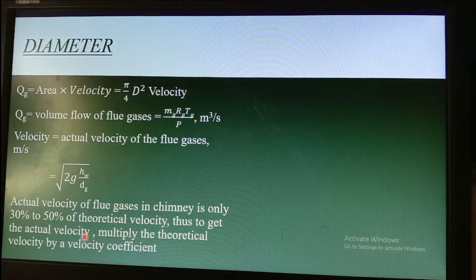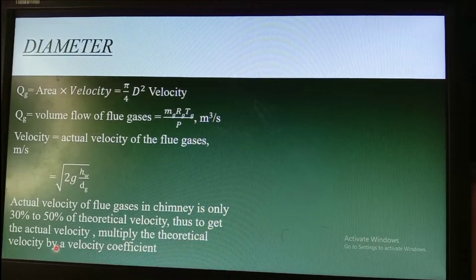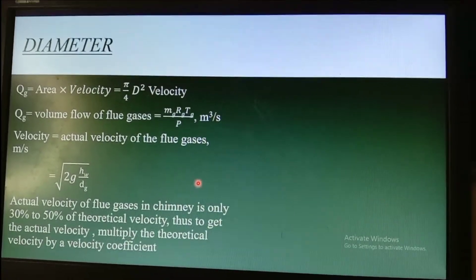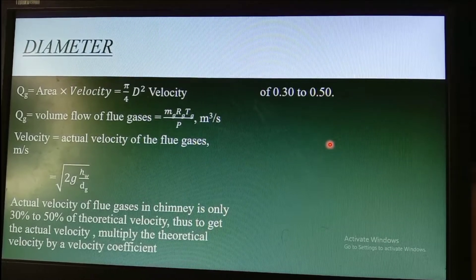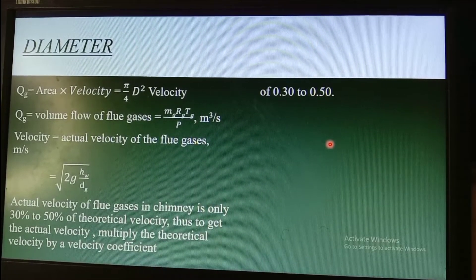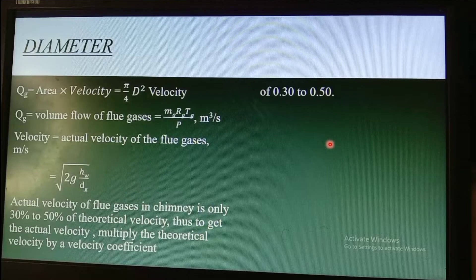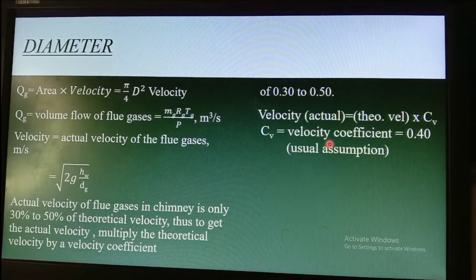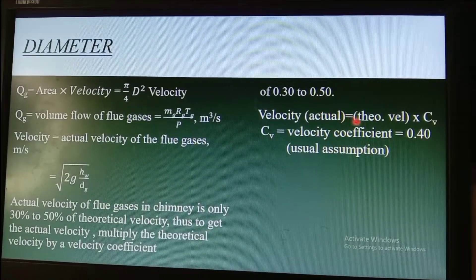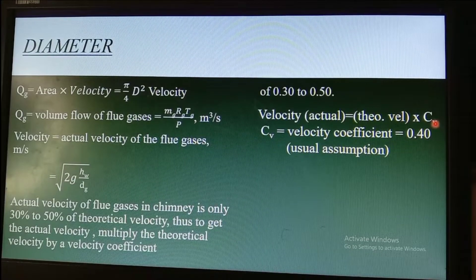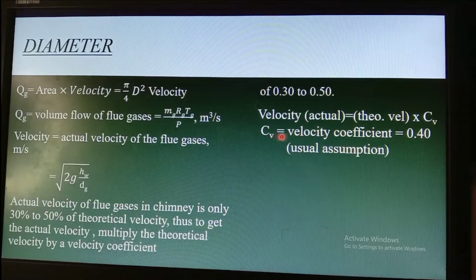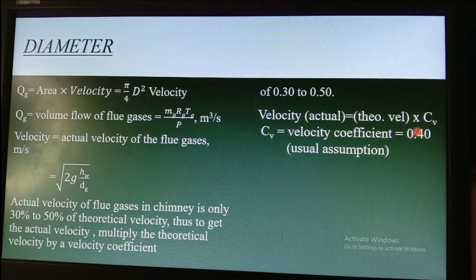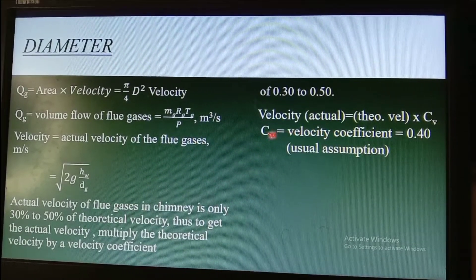The actual velocity shall be the theoretical velocity multiplied by a coefficient Cv of 0.3 to 0.5. In actual practice, we use Cv = 0.4. So the actual velocity equals the theoretical velocity times Cv, where Cv = 0.4. This 0.4 is the usual assumption for designing the chimney.